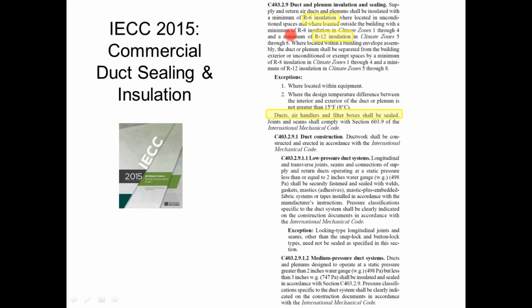However, as you're probably aware, the supply duct, if I run it to the return plenum, I don't insulate it, it very well could sweat. So I'm probably going to want to insulate it for other reasons other than energy code. So the energy code, the answer is no, Tom, but from a good application standpoint, yeah, I would insulate my supply duct when it's inside my return plenum, because you could have some condensation issues when you run 55-degree air through a relatively humid space, and plus you also lose some of your BTU capacity that leaves the ductwork and goes back immediately into the return side instead of going into the space. So I would insulate it even though the code doesn't currently require you to do that in your scenario.